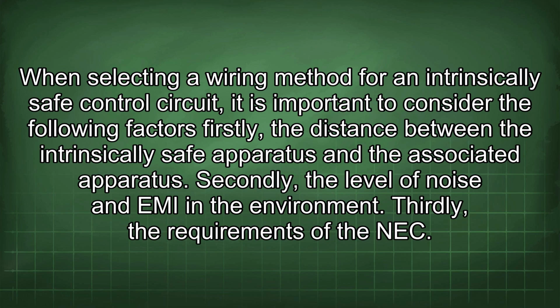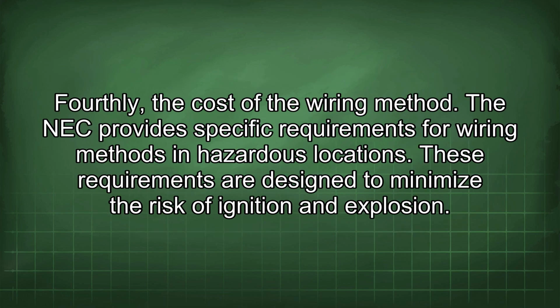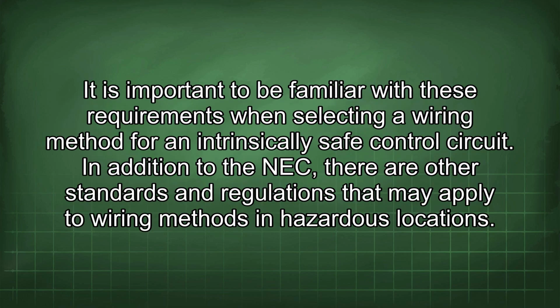When selecting a wiring method for an intrinsically safe control circuit, it is important to consider the following factors. Firstly, the distance between the intrinsically safe apparatus and the associated apparatus. Secondly, the level of noise and EMI in the environment. Thirdly, the requirements of the NEC. Fourthly, the cost of the wiring method. The NEC provides specific requirements for wiring methods in hazardous locations. These requirements are designed to minimize the risk of ignition and explosion. It is important to be familiar with these requirements when selecting a wiring method for an intrinsically safe control circuit.